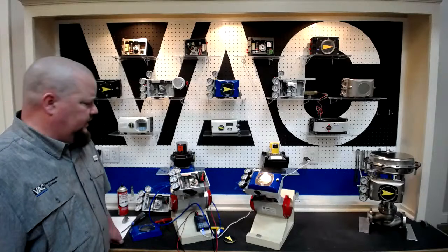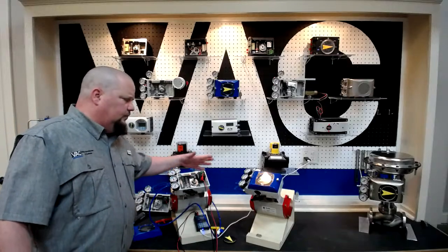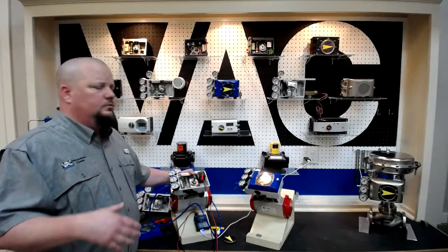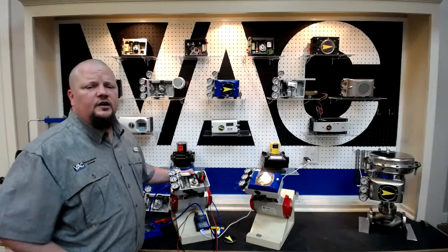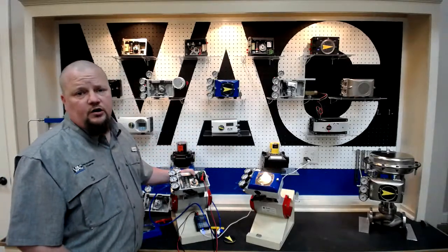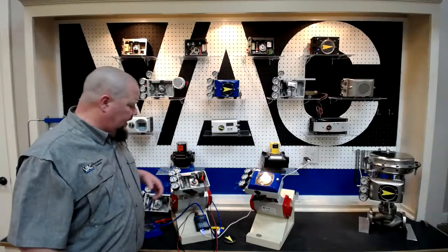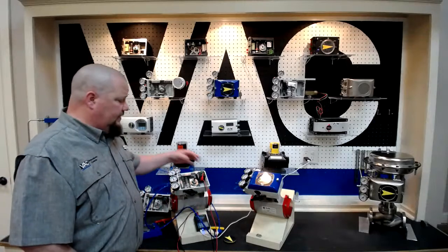But there's a couple of things we can look at and check, and we'll go through those real quick. Once you've got a positioner on and it's been working for a while, you're happy with the service, but all of a sudden it's not working quite properly. Or let's start with it's just not functioning at all. You can go back to the same issues and look at the same things. Make sure you have good supply. Make sure you have a good signal.